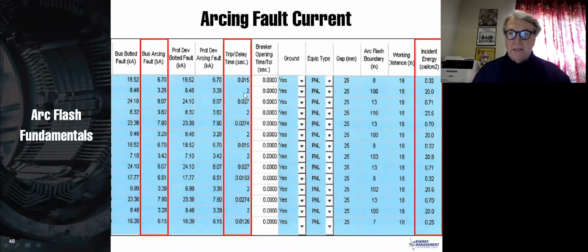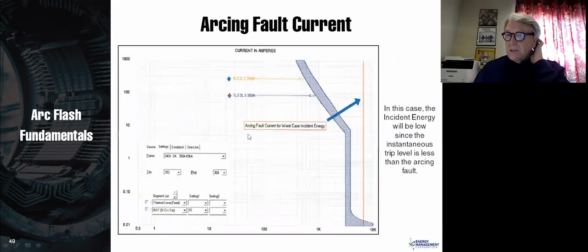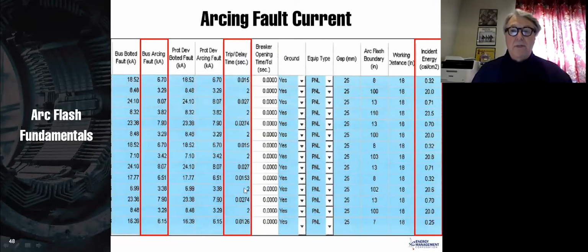Why? Because it's got a 2-second time delay. Now, why is there a 2-second time delay? We'll read the standard in a moment, but basically they're saying that if the circuit breaker or fuse trips in more than 2 seconds, we're only going to calculate the incident energy for 2 seconds, because in 2 seconds you can run. And that is literally the truth. We will see the actual statement in a moment. In 2 seconds you can run. So if you'll notice down here, 2 seconds, 2 seconds, 2 seconds, 2 seconds. That means that probably the circuit breaker or switch took longer than 2 seconds, and therefore they only calculated the energy for the first 2 seconds.